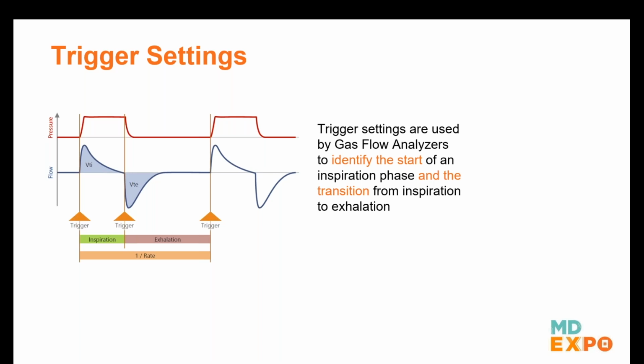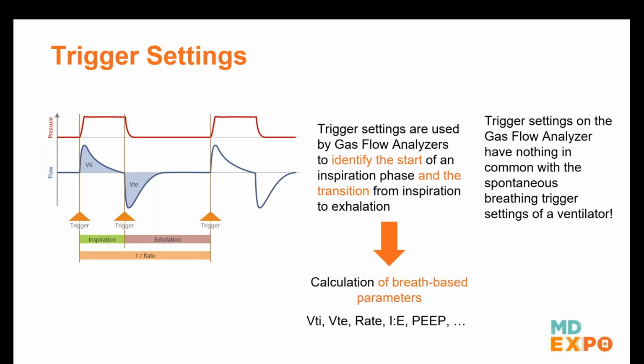So trigger settings are also used on the ventilators, but trigger settings of a gas flow analyzer are used by the gas flow analyzer to identify the breath phases of the ventilation that is going on through it. So we have typical flow waveforms and pressure waveforms here. The gas flow analyzer needs to know what is an inspiratory phase and what is an exhalation phase. The reason it needs to know that is to calculate the so-called breath-based parameters. Things like Kerwin already mentioned, tidal volumes. So how much volume has flown to the patient in the inspiratory time and how much volume came back from the patient, or the test lung in our test setup, through the gas flow analyzer.